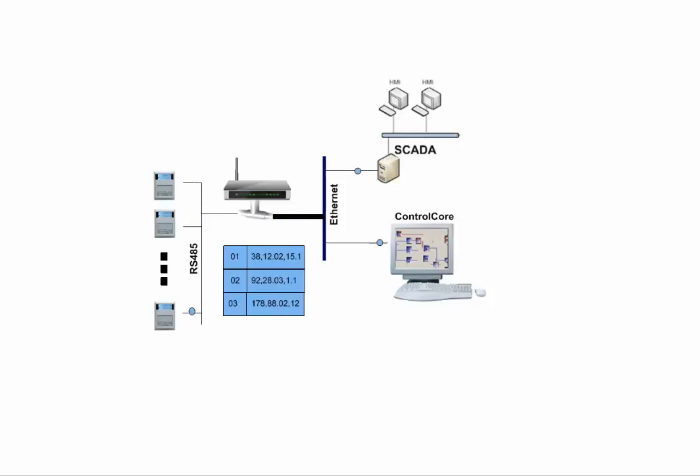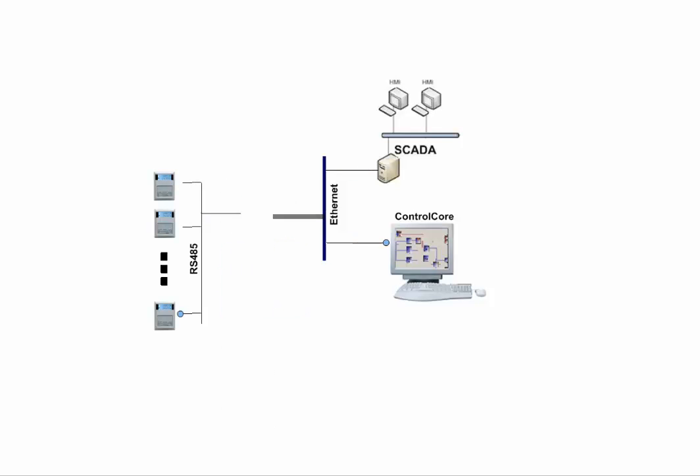Another problem that the network controller solves is peer-to-peer communications. Without the network controller, one of these devices must act as a master and perform the necessary scanning for the peer-to-peer communications to work. Problem is, if an outside application tries to communicate to this network, its request will often collide with the peer-to-peer scanning going on.